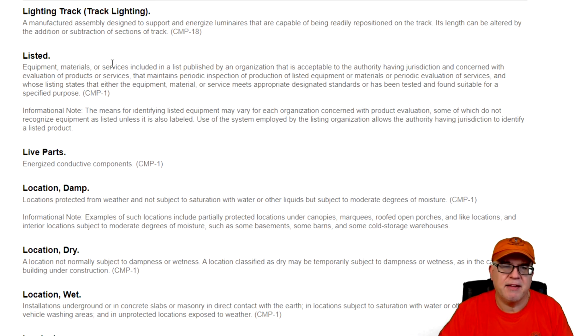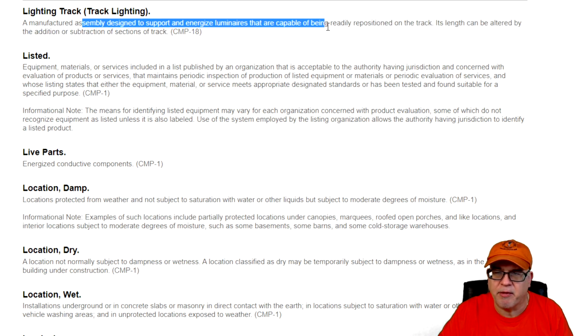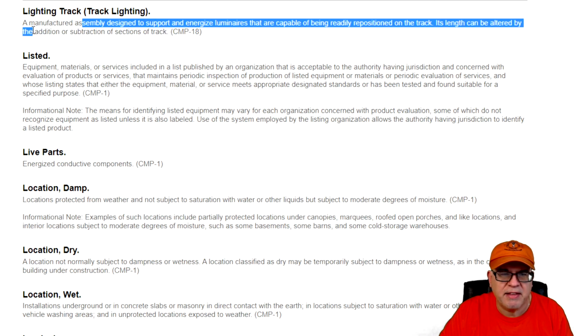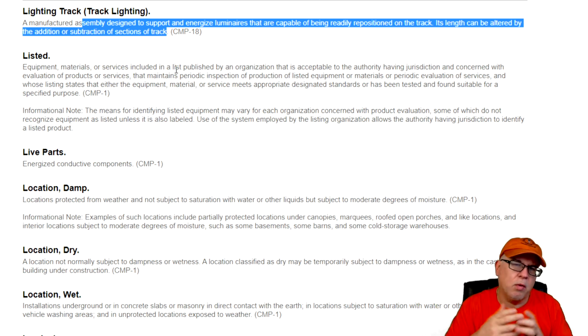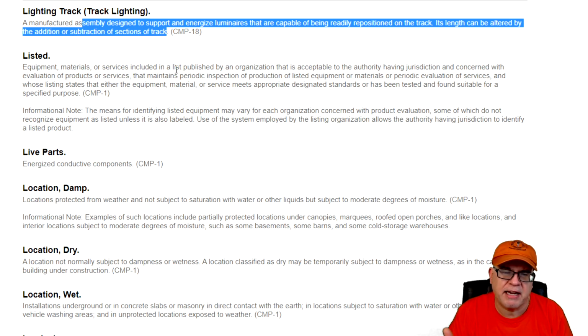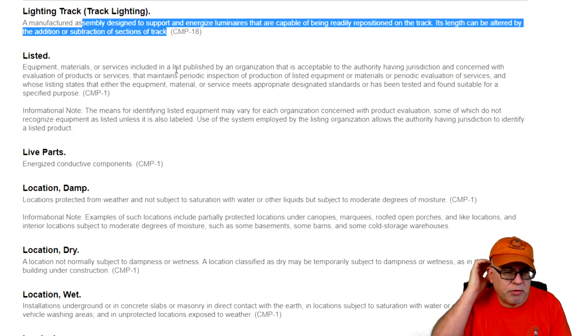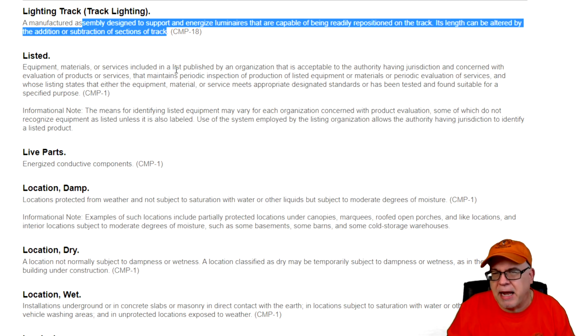It's a specific track. It says a manufacturer's assembly designed to support and energize luminaires that are capable of being readily repositioned, turned, moved, slid on the track. Its length can be altered by the addition or subtraction of sections of the track. So I can add to it, take it away, whatnot. We need to know what lighting track is or track lighting is, because when we're doing calculations in Chapter 2, which is in Article 220, we need to know for track lighting, because we have some values in VA that we have to establish for track lighting. So we need to understand track lighting a little bit.